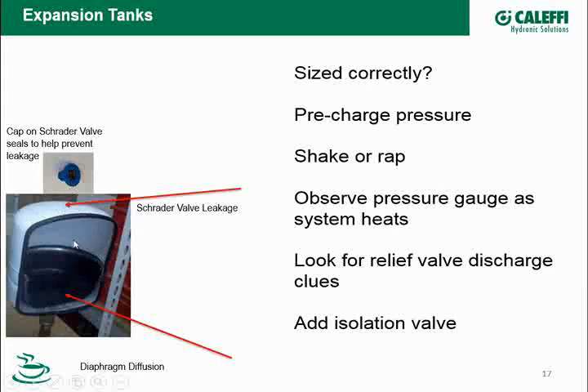Now, the other thing, keep in mind, if you're going to test this tank to see if there's an air charge, number one, you've got to isolate this tank from the system and bleed the pressure off it, so you're reading the pressure in the tank, not the system pressure. But keep in mind that every time you put a gauge on there, year after year, every time you go back and check it, you're going to let a little bit of air out of this pre-charge. So at some point you might have to take your little hand pump or your compressor back and repressurize this tank because you've let some air out of it.